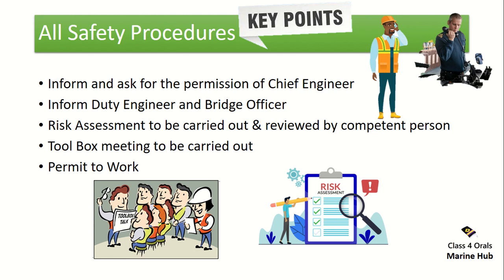The first point is: always inform and ask for the permission of the chief engineer — without any information or permission, please do not proceed for the maintenance. Second, inform the duty engineer and the bridge officer, because in case they want any heavy equipment which requires more generators, they will already know that maintenance is going on and will not request heavy equipment usage.